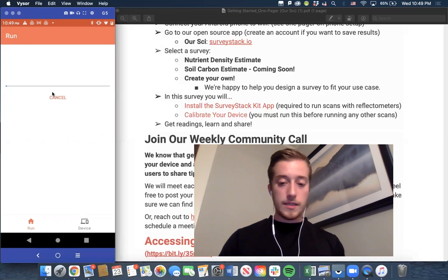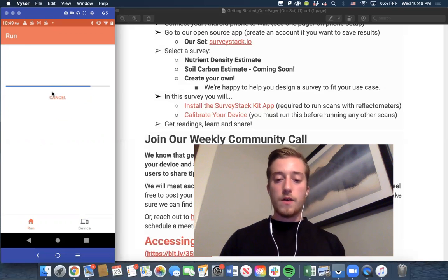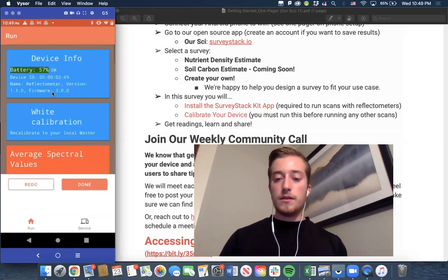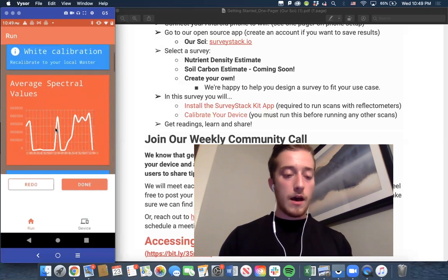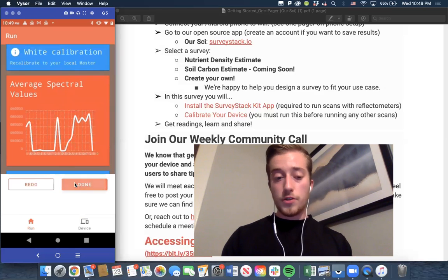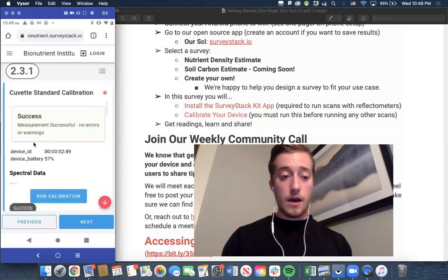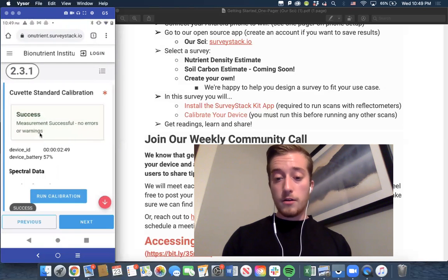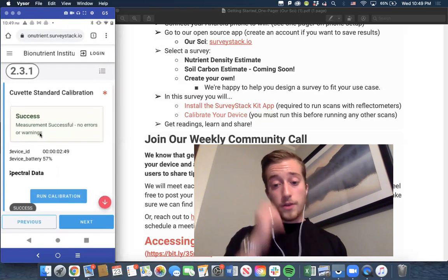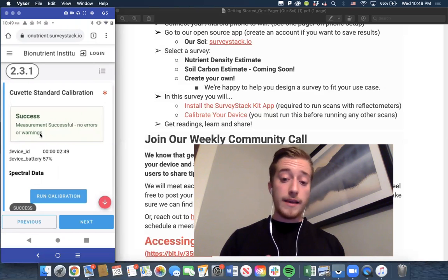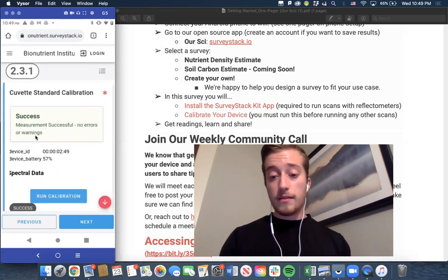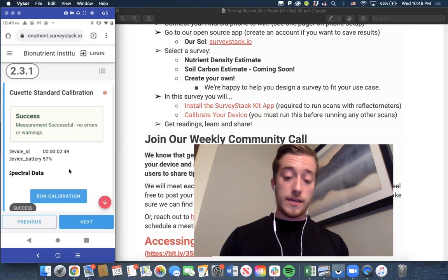And again, this barium sulfate is a highly reflectant substance, so this is seen as the most reflectant thing that your device will encounter. You can look at these results, or you can just click done and you can see your success. If you get a warning error, go back and make sure that your cuvette standard is clean, your light guide on the surface of the reflectometer is clean, and that you've positioned it correctly, scanning the correct face of the cuvette standard.